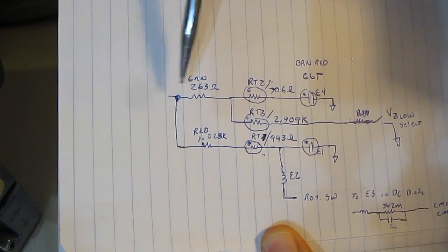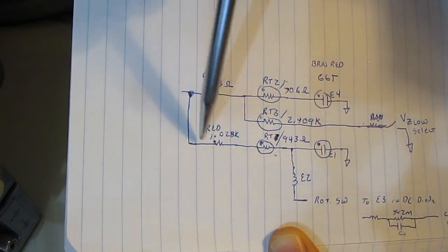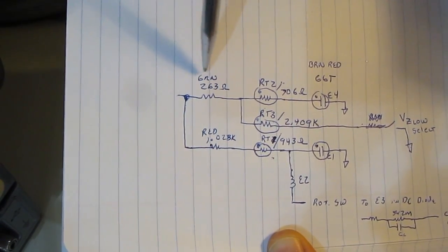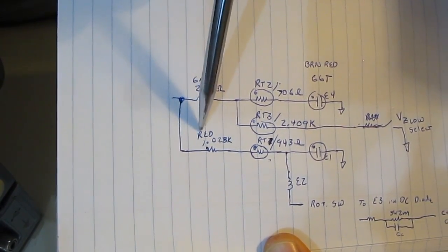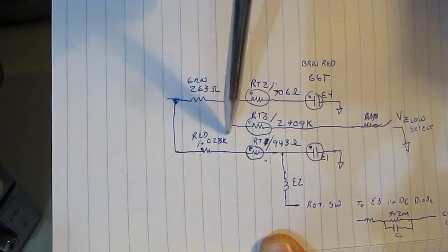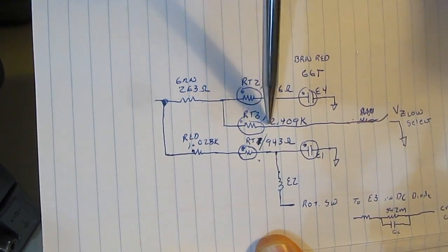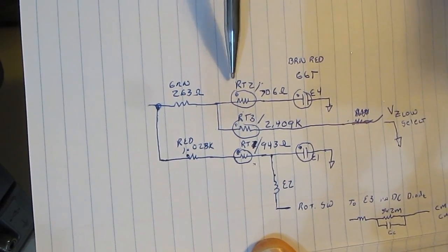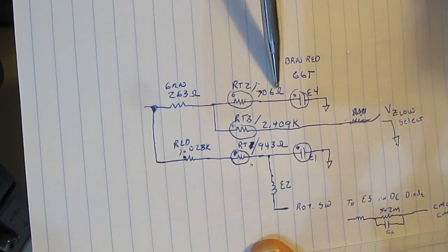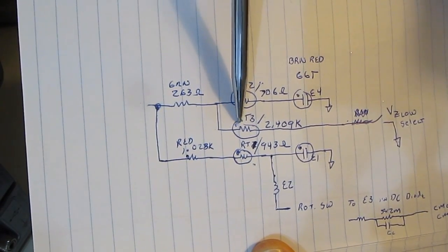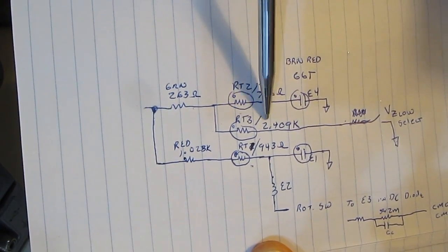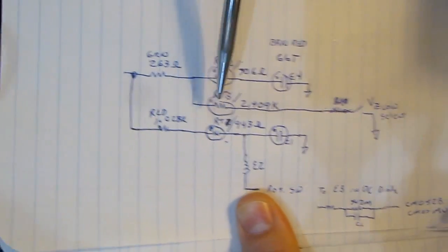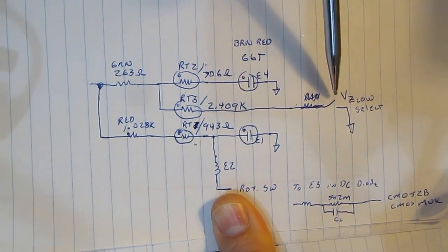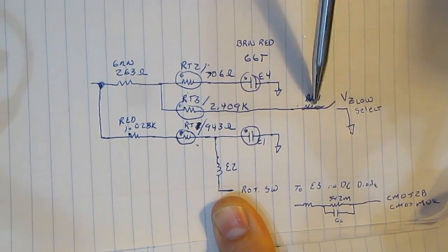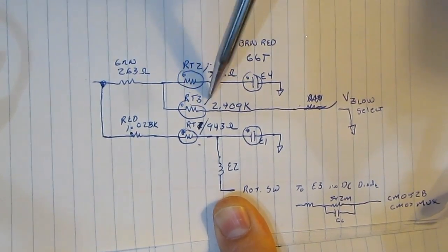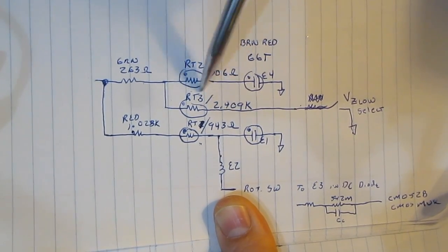I traced out the front end of the meter, so the voltage input comes in. This goes to the two high voltage resistors. The green banded one is 263 ohms. The red banded one is 1.028K. The green branches off to two PTCs. The first one is RT2. It measures 706 ohms. And it also branches to RT3, which is a 2.4K ohm. RT3 runs to the selector switch. When VZ low is selected, it grounds this PTC. So this PTC provides their low impedance path.